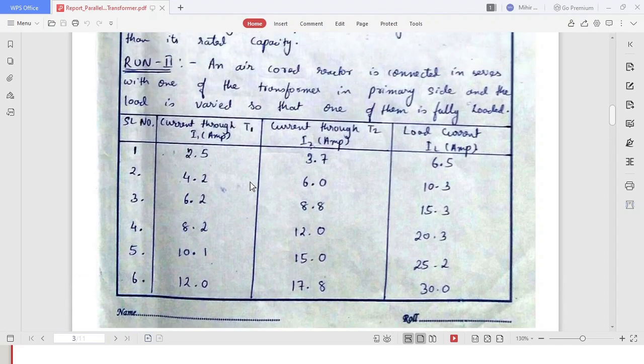Now with reactor you see that here 2.5 and 3.7. So you can easily say that where the air core reactor is connected, here 4.2 and 6.0, 6.2 and 8.8. Here you see that this value is lesser than the transformer 2 values. This is because in transformer 1 the air core reactor is connected, so its impedance gets increased. So the current drawn by transformer 1 will be lesser than transformer 2.